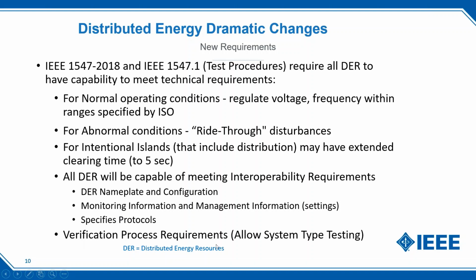And the last area of change is the verification process. There are some new steps related to verifying that the design meets the local requirements, as well as the new rules allow system type testing. So for example, instead of the previous rules just talked about an inverter box meeting technical requirements, you're now able to test an entire system, and that could be a master controller, several inverters, energy storage devices, and solar PV, as long as the manufacturer sees it as an economically viable investment. They can type test that whole system, which will streamline the integration and commissioning process.